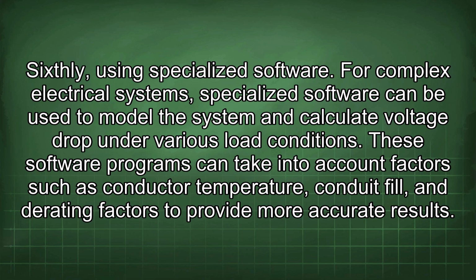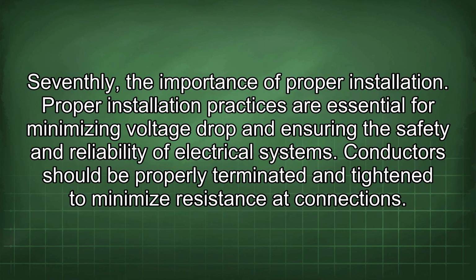For complex electrical systems, specialized software can be used to model the system and calculate voltage drop under various load conditions. These software programs can take into account factors such as conductor temperature, conduit fill, and derating factors to provide more accurate results.